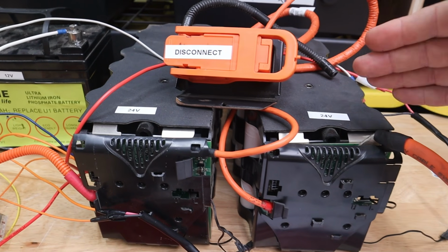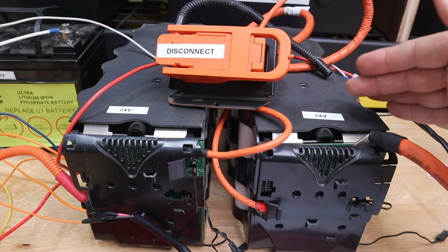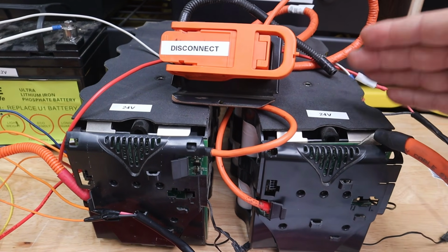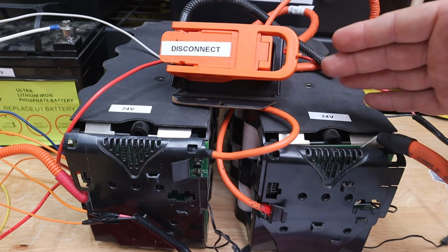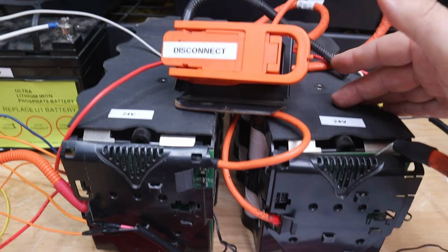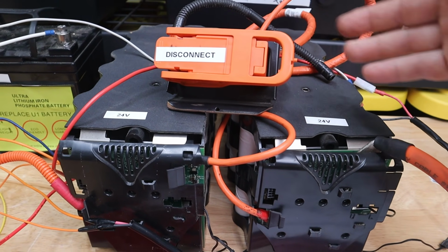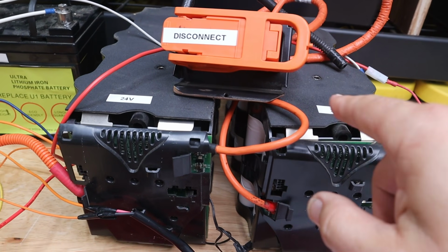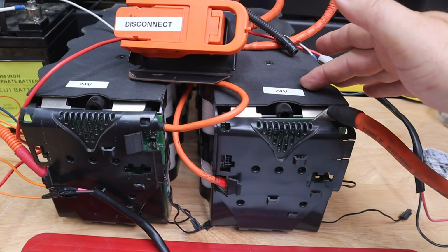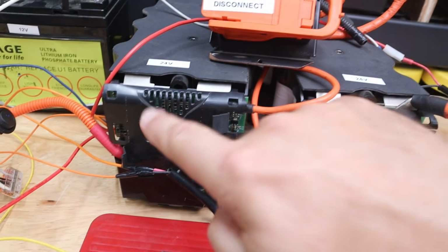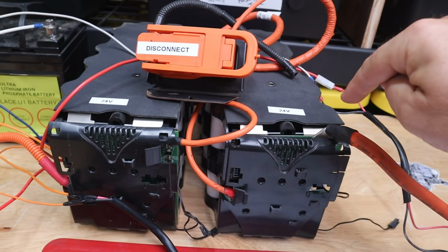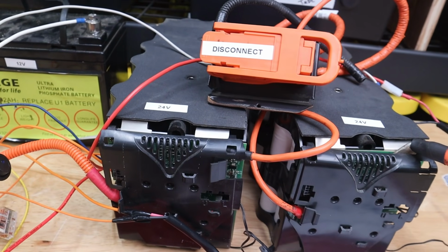Typically, a disconnect is in the middle of a battery pack, so it takes it from high voltage, let's say 400 volts, down to 200 volts when you pull the disconnect. I'm doing that here, even though it's not nearly as important with just a 48 volt setup. This is the negative side, this is the positive side, 24, 24, 48 volts.